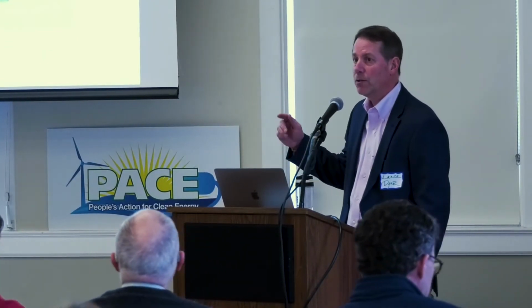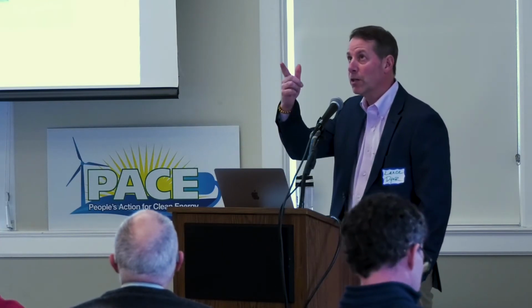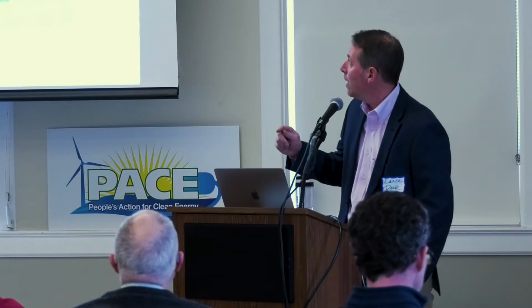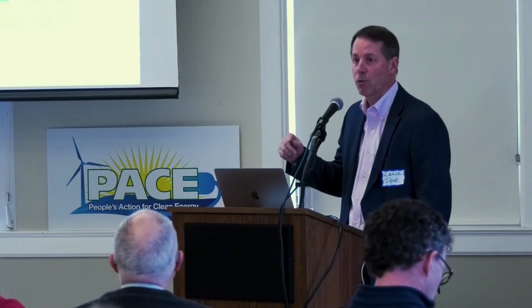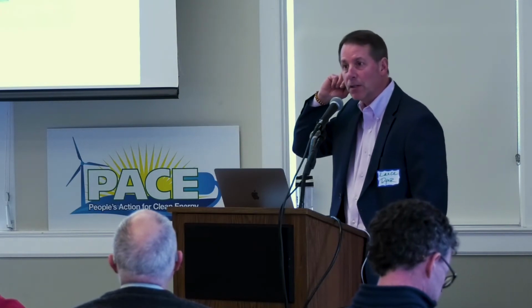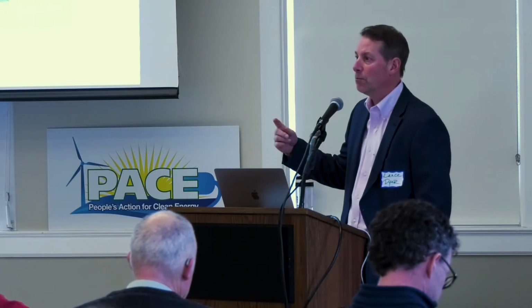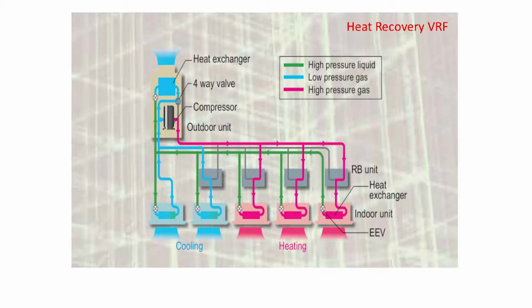Heat pumps are historically two-pipe systems. We're supplying refrigerant to indoor units, indoor fan coils, indoor cassettes, and other types of indoor units. Then you have a gas or vapor line that, once the heat is pulled out of the refrigerant, sends it back to the condensing unit to turn it back into a liquid and complete the cycle. It can be piped very similarly to how you would pipe a boiler system. There are a number of trained contractors throughout the state of Connecticut, and a number of different brands. We happen to represent Fujitsu, but there are others on the market today, including Mitsubishi, LG, Samsung, Daikin, and others. The second type of system is called heat recovery, and with this you see a 3-pipe system instead of 2.